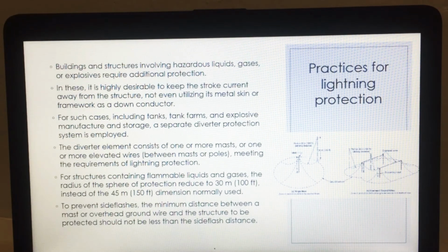And the practices for lightning protection: buildings and structures involving hazardous liquids, gases or explosives require additional protection. In this case, it is highly desirable to keep the stroke current away from the structure, not even utilizing its metal skin or framework as a down conductor. For such cases, including tank farms and explosive manufacture and storage, a separate diverter protection system is employed.